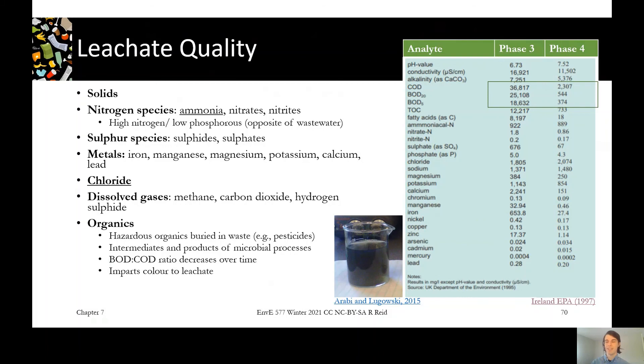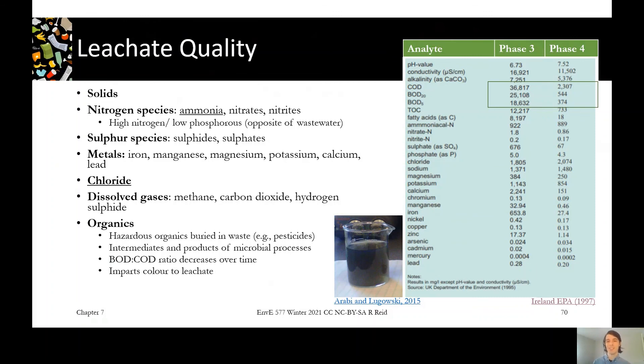Going back to that phase three part of operation — earlier on in the landfill life, if you look at the BOD5 to COD ratio, it's about 50%, and then later on it goes down to about 15%. So it really changes over time, and that's one of the complications with leachate treatment. It's not like domestic wastewater where you're getting a constant stream of fresh sewage. Once your landfill is closed, the leachate just gets older and older and keeps changing, and that's something you need to plan for when thinking about how to manage the leachate.